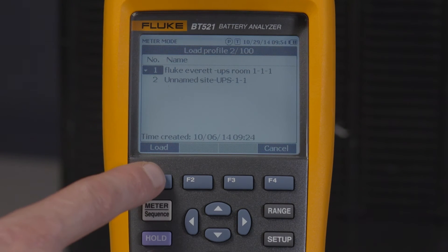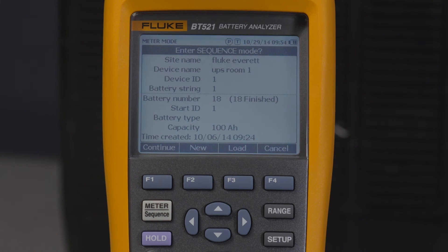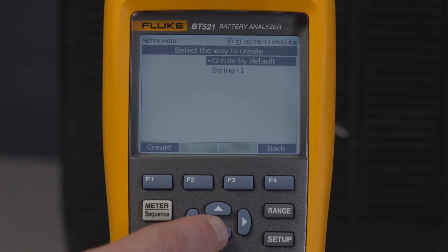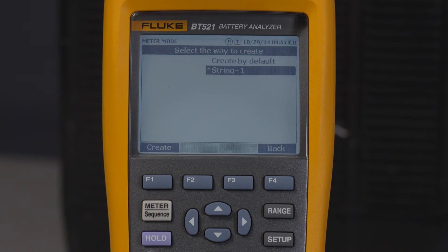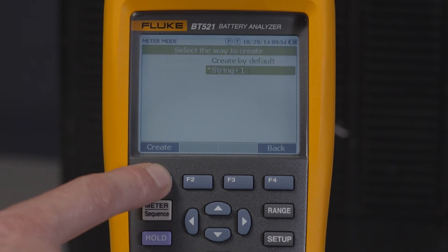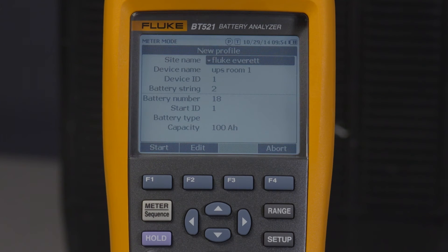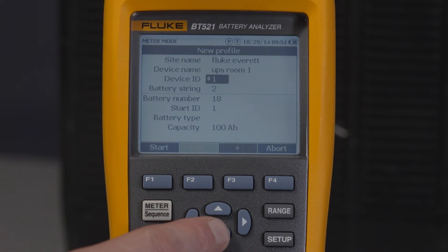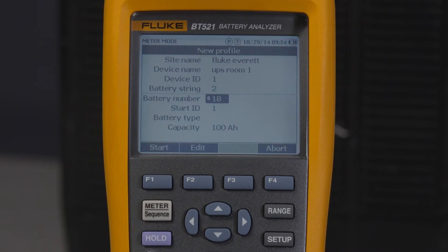Press the load soft key and press the new soft key to modify this profile. Select string plus one — this simply takes the data from the previous profile and adds one to the value of the battery string. This makes it easy to test the next battery string without repeated data input, which is especially helpful in an infrastructure with multiple battery strings that have the same battery type and number. From here you can also edit the profile further in the same way as the profile was created earlier in this video.